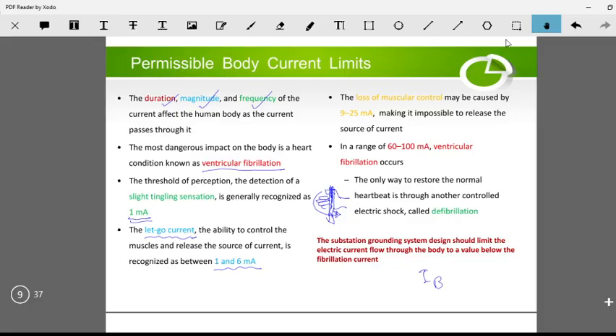If the current is between 9 and 25 milliamperes, you lose muscular control, meaning you can't control your body anymore. Because of that, once you grab onto something, you may not be able to let it go, so the current will continuously flow through your body unless the trip occurs or something else happens.